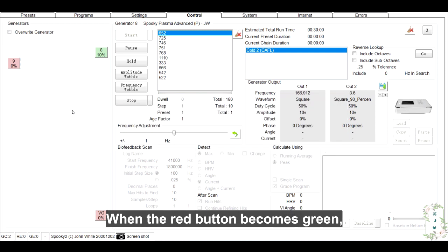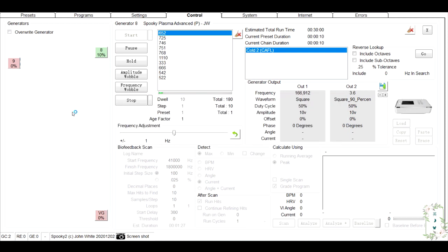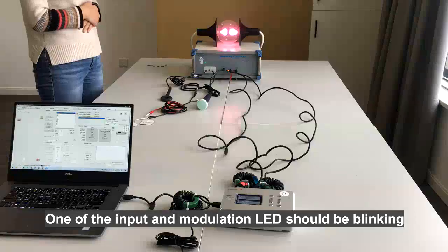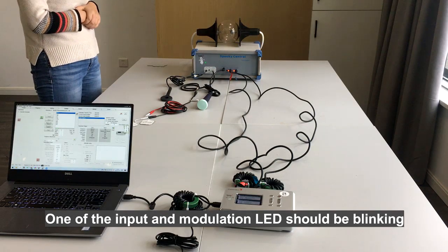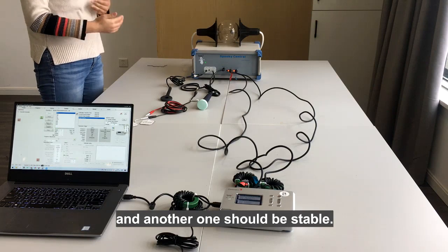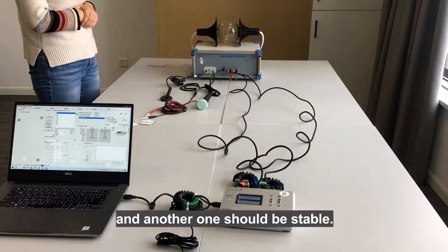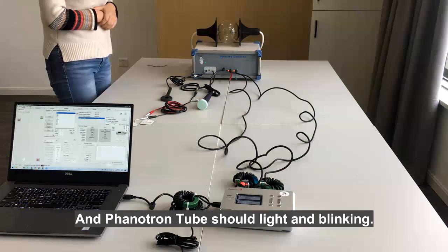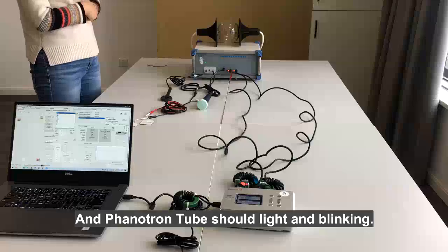When the red button becomes green, which means the program is running, one of the input and modulation LEDs should be blinking, and the other one should be stable, and the Phanotron Tube should light up and blink.